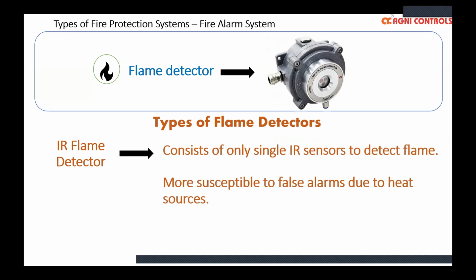Next, the IR flame detector consists of a single IR sensor to detect flame. Again, IR is also available in the atmosphere. Whenever there is heat generated, it emits a considerable amount of IR radiations. So these detectors are more prone to false alarms in cases where there are hot body objects nearby.